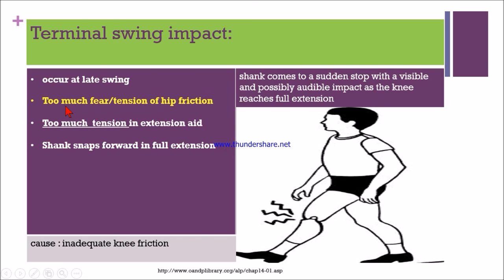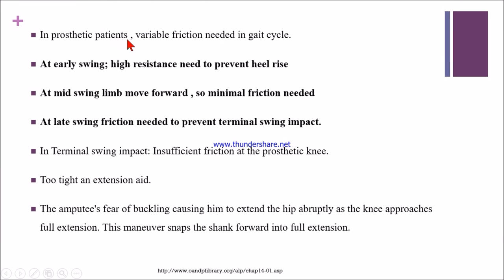To remember the causes, think of too much fear or tension of hip friction. In prosthetic patients, variable friction is needed during the gait cycle. At early swing, great resistance is needed to prevent heel rise. At mid swing, the limb moves forward and minimum friction is needed. But at terminal swing or late swing, more friction is needed to prevent the swing impact.